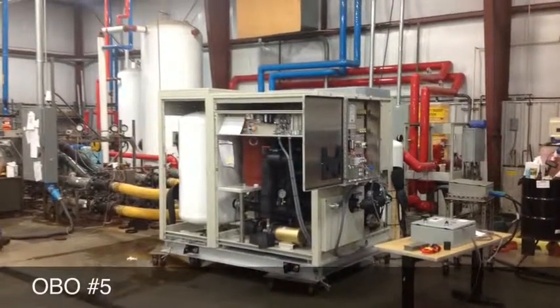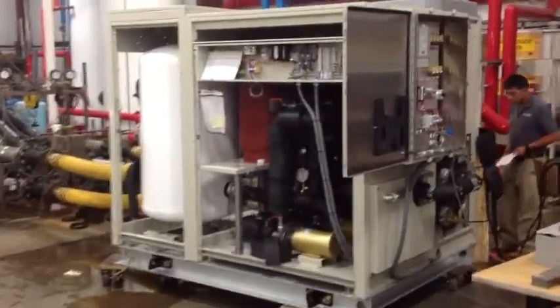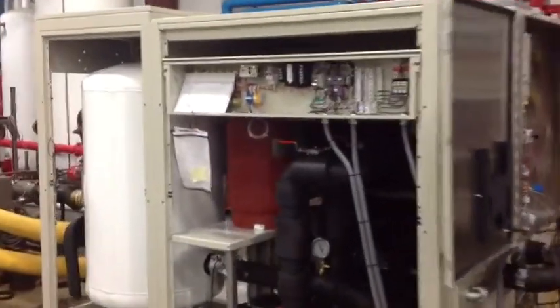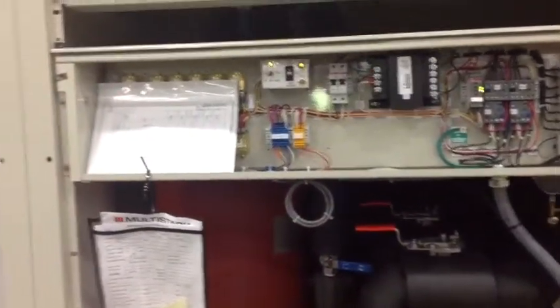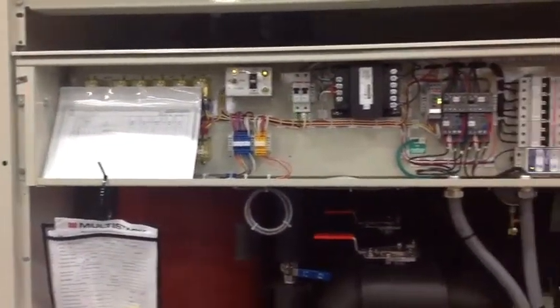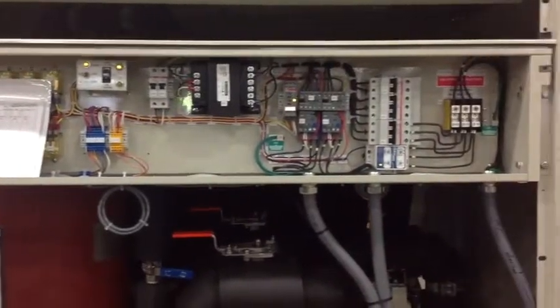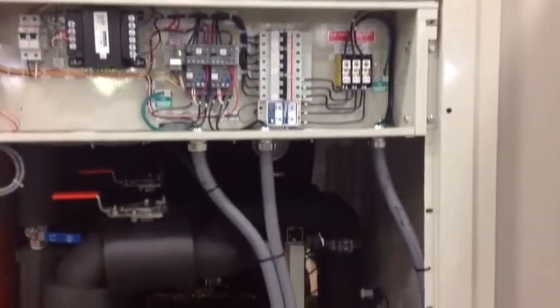This is a wide-angle view of the chiller package with a single independent circuit mechanical module, a pump module with 2 pumps, and a storage tank. In the upper portion of the pump module here you can see the maroon colored bladder type expansion tank. This is the pump control panel.